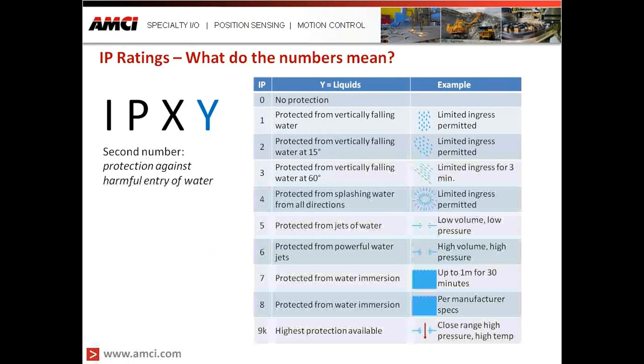The second number covers protection against liquids. In some instances, it's not just protection against harmful entry of water — in some cases there is a limited permissible entrance of liquid into the enclosure, where any liquid that does get inside will have no harmful effects. This may or may not be appropriate for things such as sensors or motors, but if you think about an electrical cabinet, we may get a small amount of liquid inside the unit, but as long as it has no harmful effects on the overall cabinet operation, that's what the IP rating would consider permissible limited entrance.